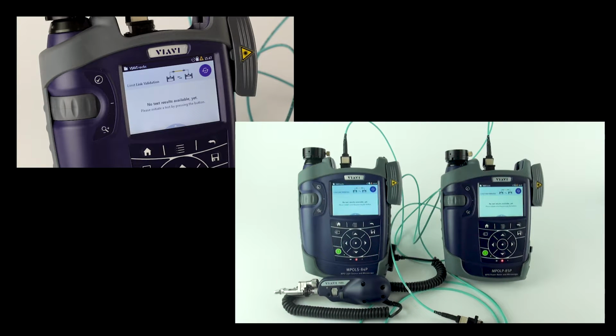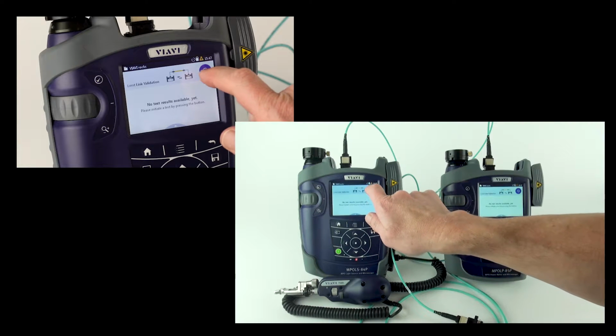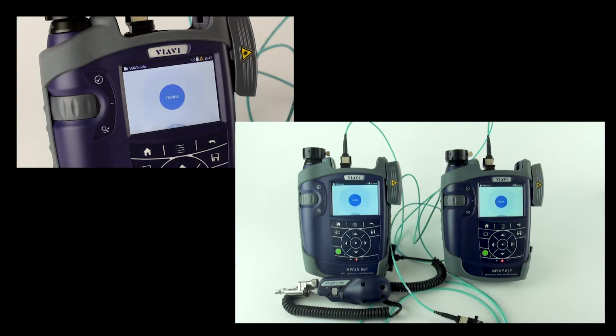Once I connect up, you'll hear the units will beep at each other and tell you that they're connected, and I simply press the auto test button. It tells me that it's testing. It takes somewhere around 6-7 seconds to test all 12 fibers. Remember that it's doing loss, length, and polarity here in this test.